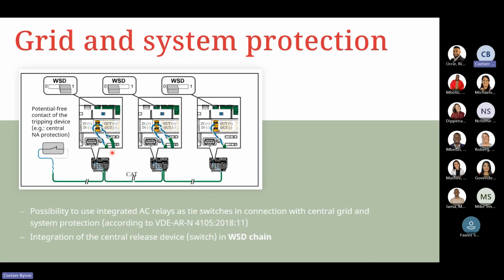So again, it is bridged from factory. If you're not using it, you don't have to stress about doing any additional wiring or switching the WSD function on or off. But if we are using multiple inverters, we then need to make sure that we're using a Cat5 twisted pair for both in and out to allow us to communicate correctly with the WSD. What we'll also need to do is set the master to 1 and the slaves to 0 respectively in the system that we are using the WSD.